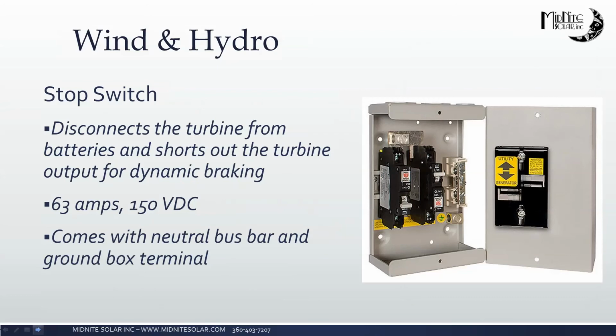It does not drop the voltage of the turbine. So I have had that call a few times. Will the clipper take my 600 volt turbine and limit it to 250? It will limit it to 250, but the turbine's going to be at 250 as well. So it's going to be horribly stalled. So it is not a DC to DC converter. It is just a load dump for the turbine.